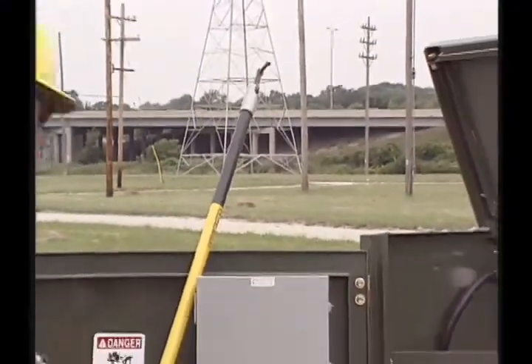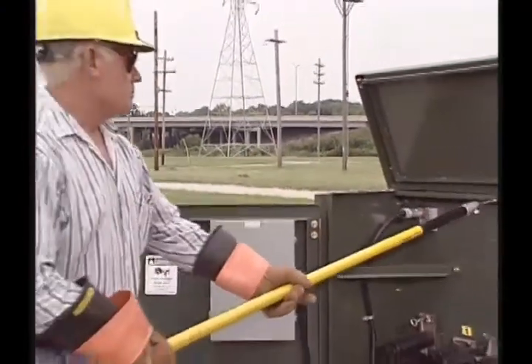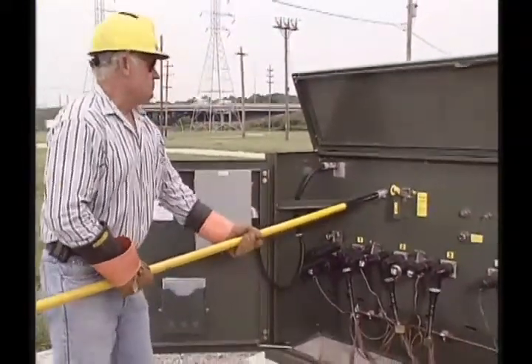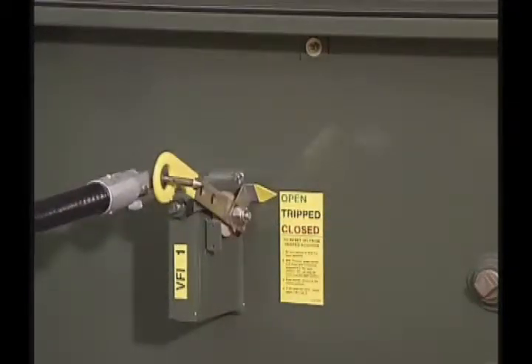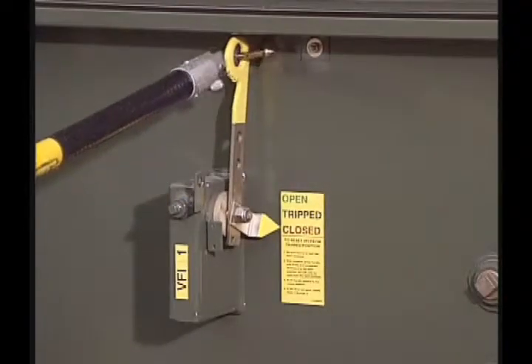Manually open the VFI by pulling the operating handle to the open position. To reset the mechanism, pull the operating handle until the latch resets. After the latch is reset, the VFI mechanism can then be closed by pushing the handle to the closed position.